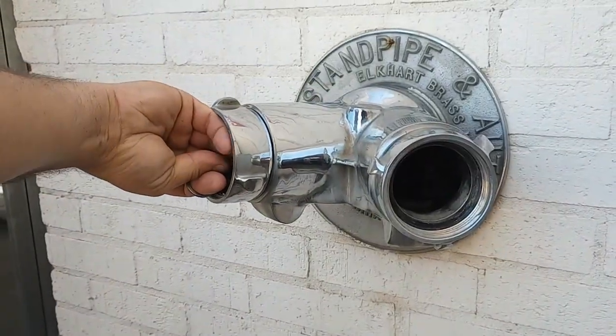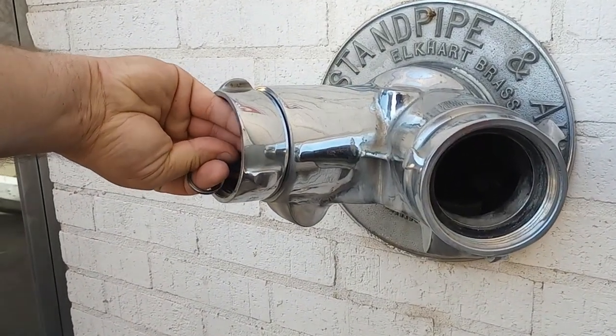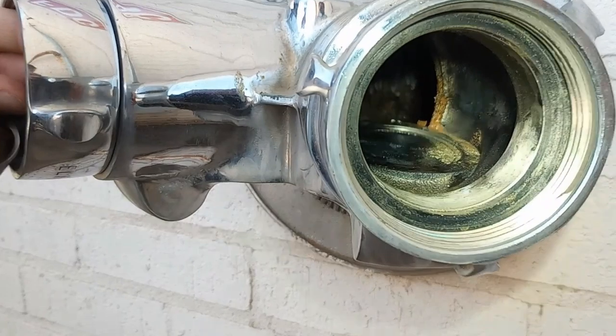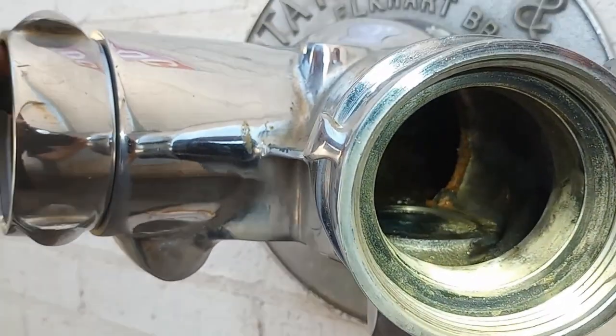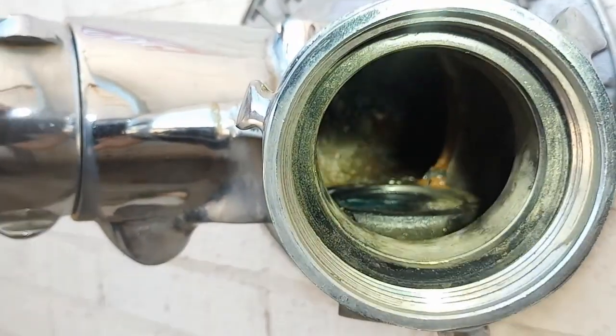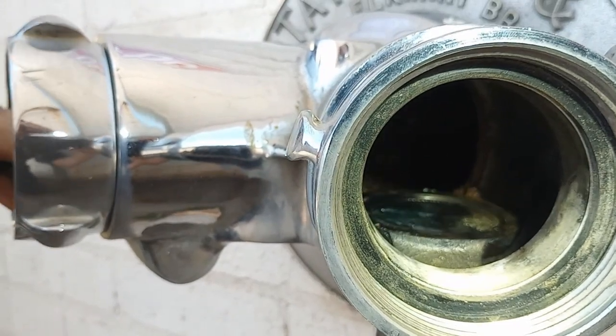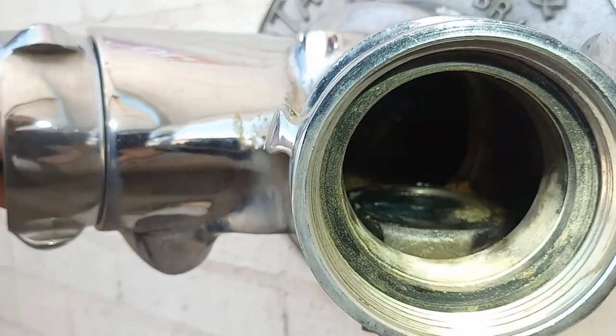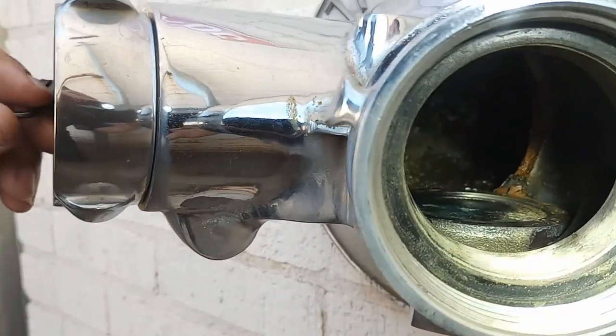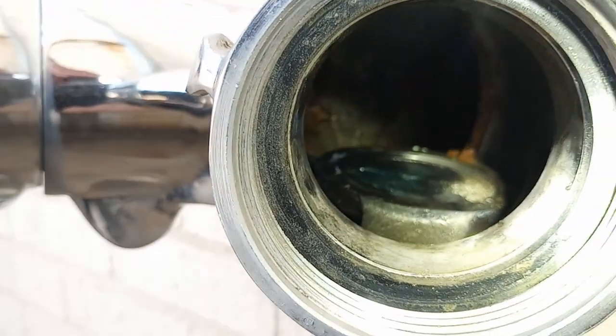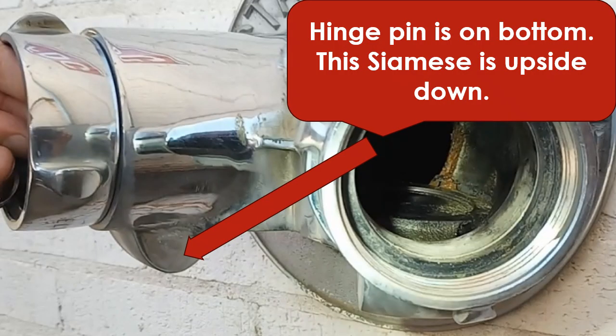Upon further investigation of this Siamese, we see that there is a clapper valve and it flips upward. You can see in here a slight movement. So if I can get under it... it is. As we looked at it, we identified that obviously this Siamese is just flipped upside down. So you can see the hinge pin is on the bottom, and therefore the clapper is not going to work.